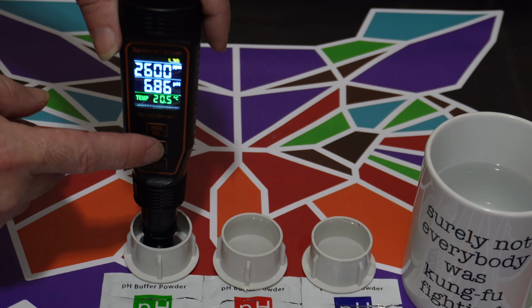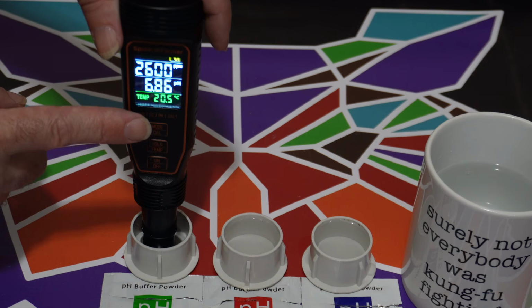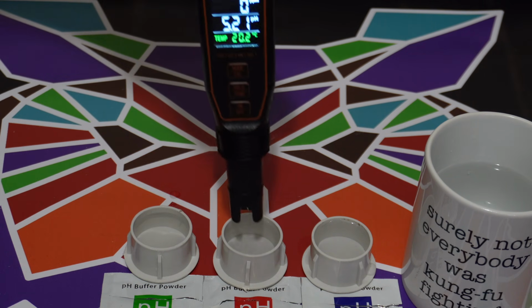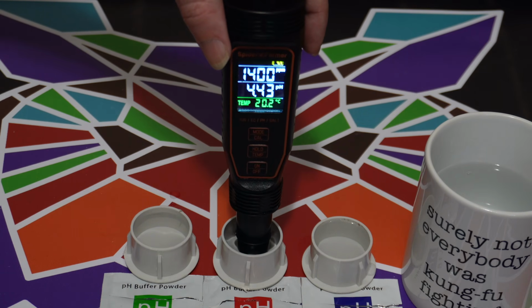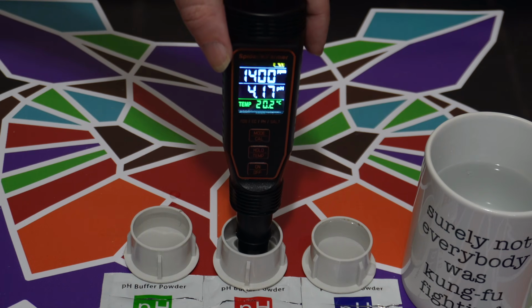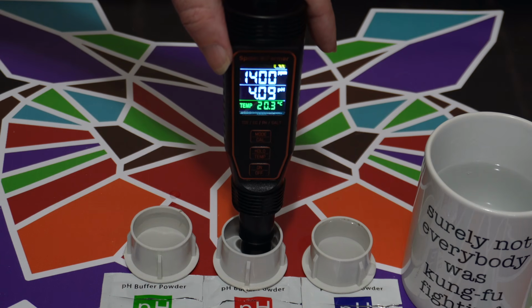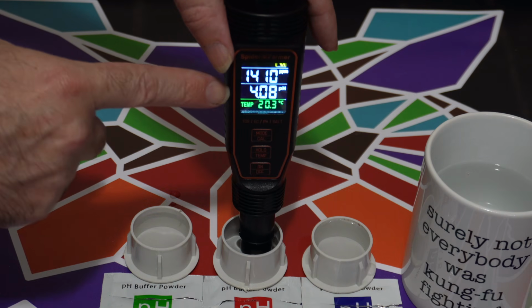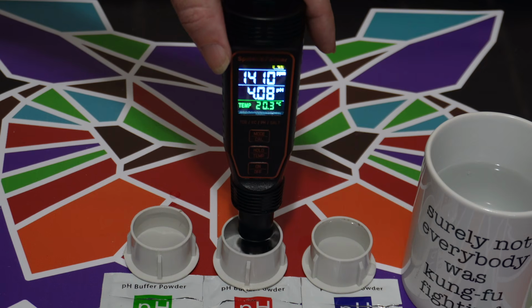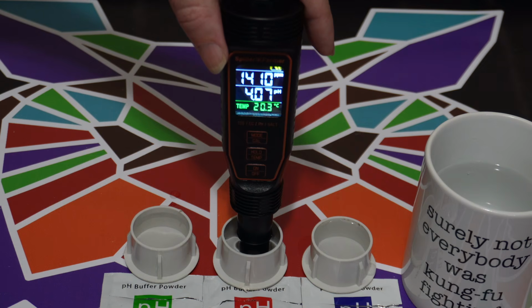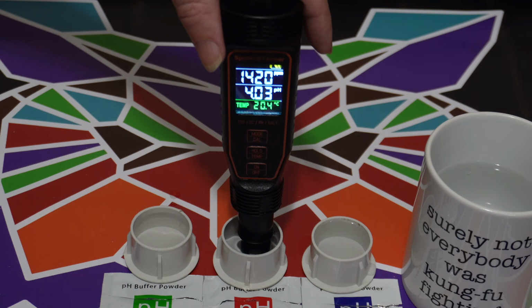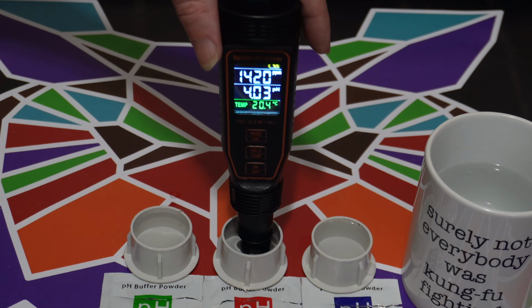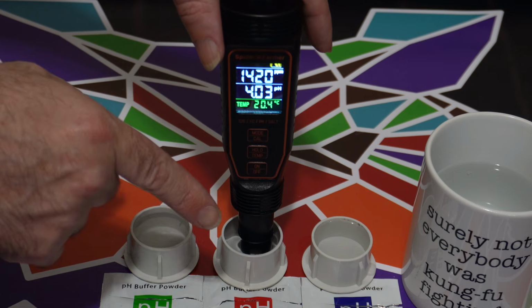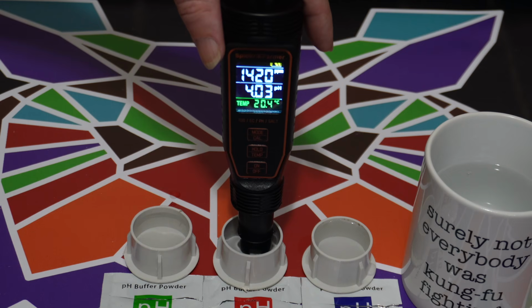All right, 6.86 is where we're at in the 6.86 calibration solution. This thing looks like it's good. And again, because I can, I'm just going to dump this into that 4.0 solution, and it should come up to 4.0 down here in just a moment. Again, sometimes it could take about 15-20 seconds before the pH actually properly reads. So be patient, but let it do its thing. We're at 4.03 right now. So that's pretty close to on. When it was spot on the 6.86, 4.03, so slight variation there, but it's within the realm of reason.